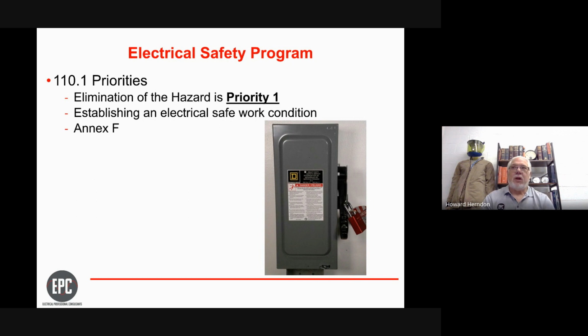We've got a job I'm working on with a consulting engineer and electrical contractor at the Clark County courthouse with some HVAC equipment change out. If you know a little about electrical safety requirements, this piece of equipment had about 75 calories of energy at it. At 75 calories, even with PPE on, if something happens, that PPE is nothing but a body bag for the coroner to pick you up in. Typically over 40 calories, we would not allow someone to work around that piece of equipment.